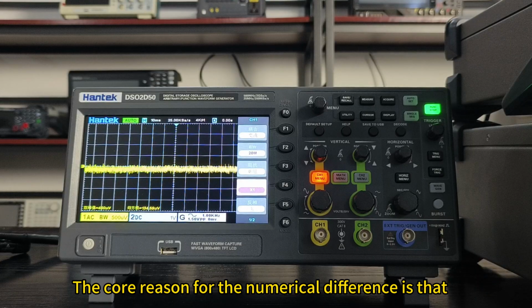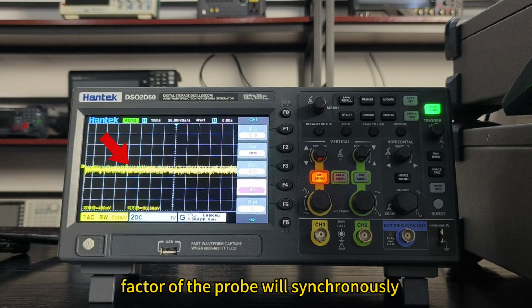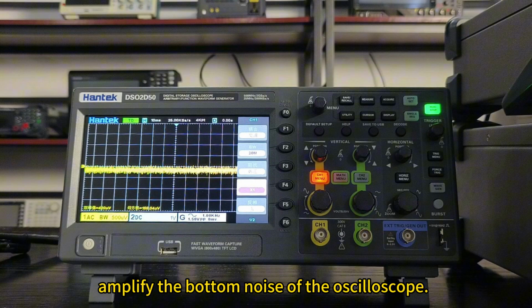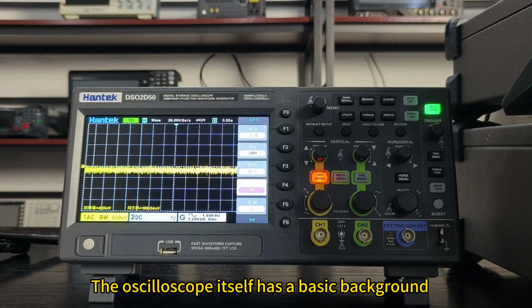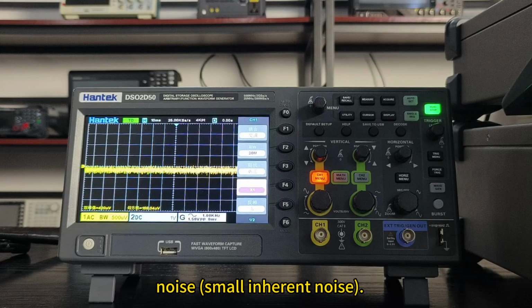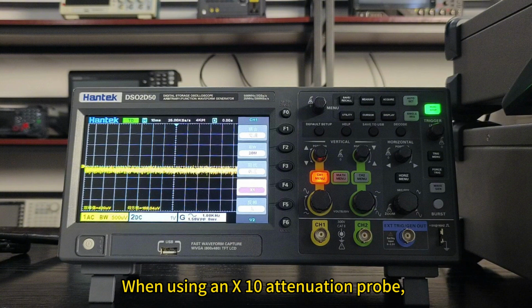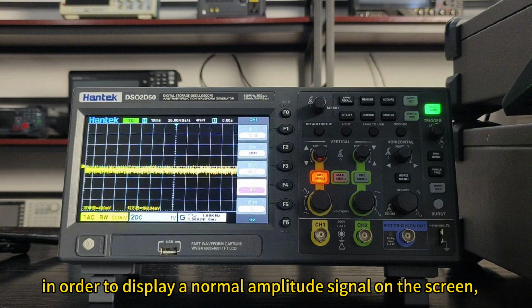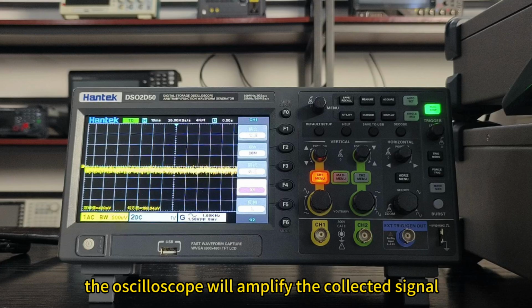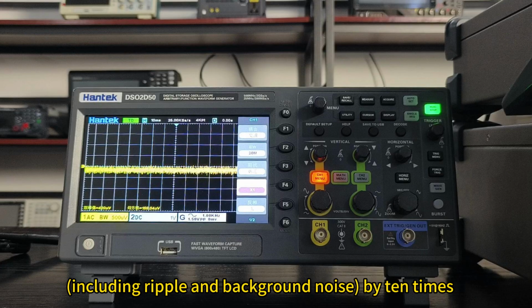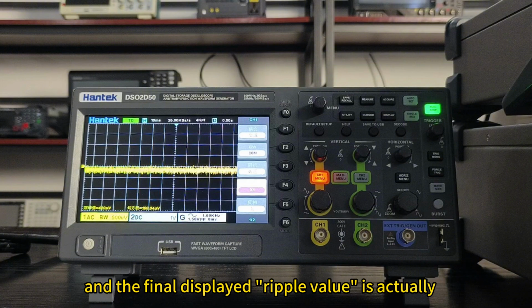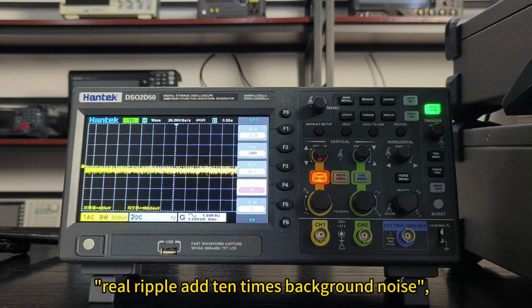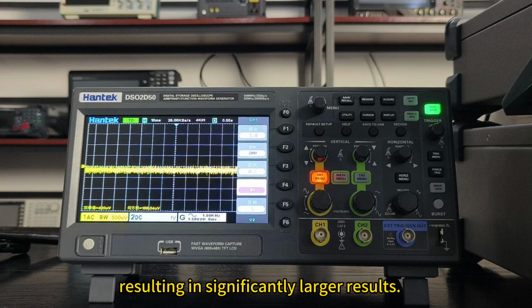The core reason for the numerical difference is that the attenuation factor of the probe will synchronously amplify the bottom noise of the oscilloscope. The oscilloscope itself has a basic background noise, a small inherent noise. When using an X10 attenuation probe, in order to display a normal amplitude signal on the screen, the oscilloscope will amplify the collected signal, including ripple and background noise, by 10 times, and the final displayed ripple value is actually the real ripple plus 10 times the background noise, resulting in significantly larger results.